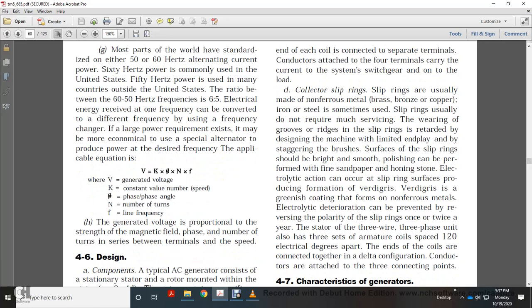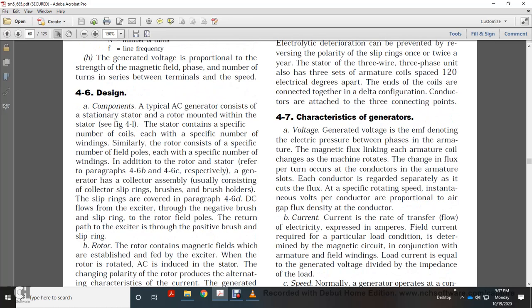Stator with three-phase unit with its three-phase armature coils spaced at 120 degrees apart. The ends of the coils are connected together in a delta configuration. Conductors are attached at three connecting points.